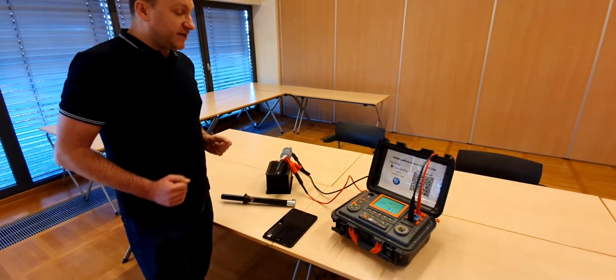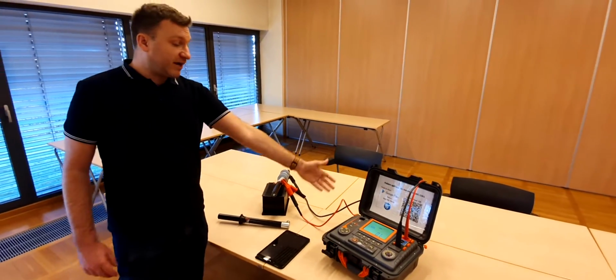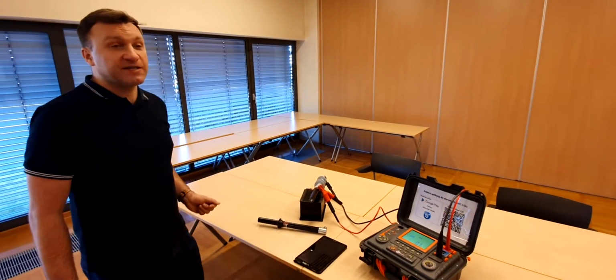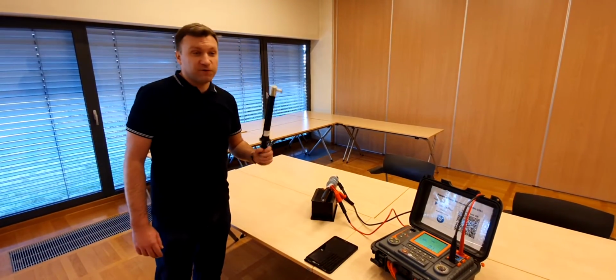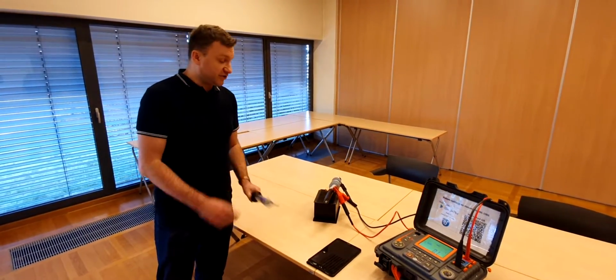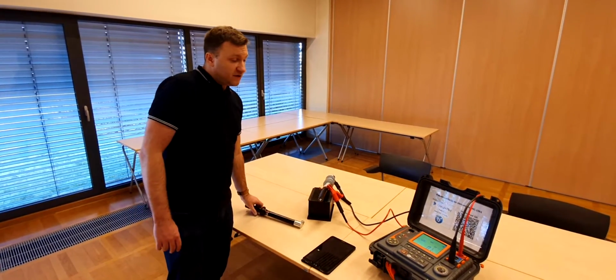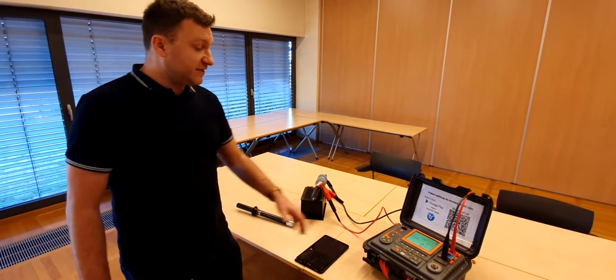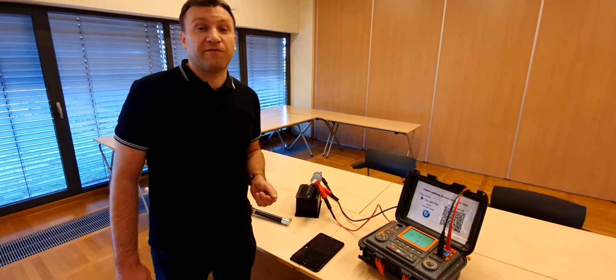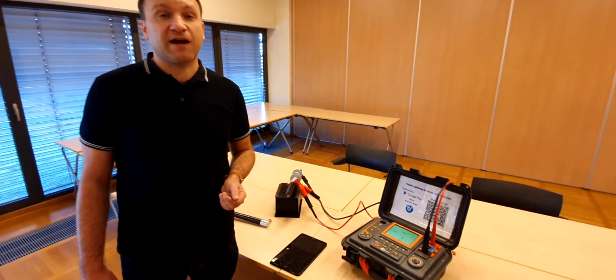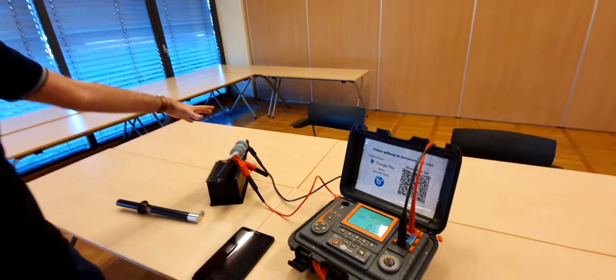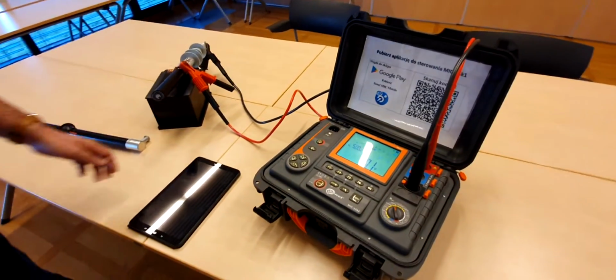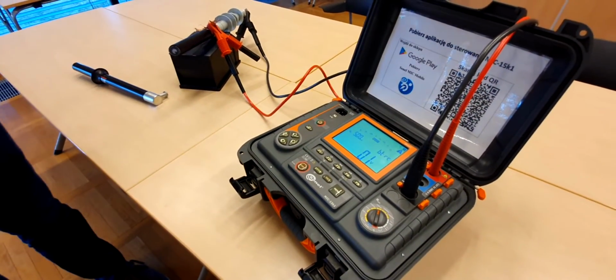Alright, so let's make the measurement. We can see over here I have the meter, I have some example of a cable, and I will create some partial discharges. So right now the meter is set with test voltage to 5000 volts. Test current is 1.2 milliamps because our cable is quite short and we won't need a bigger one.